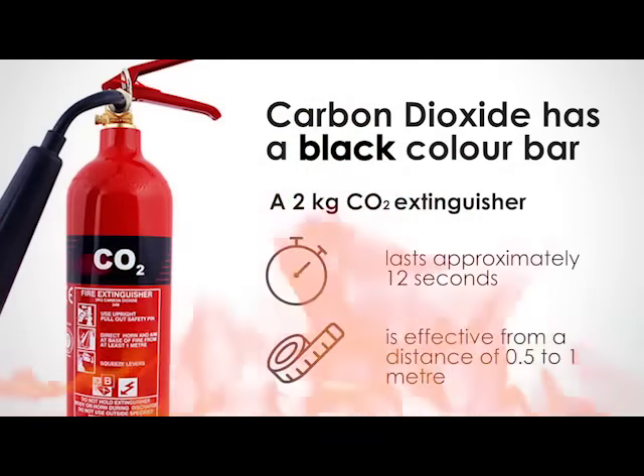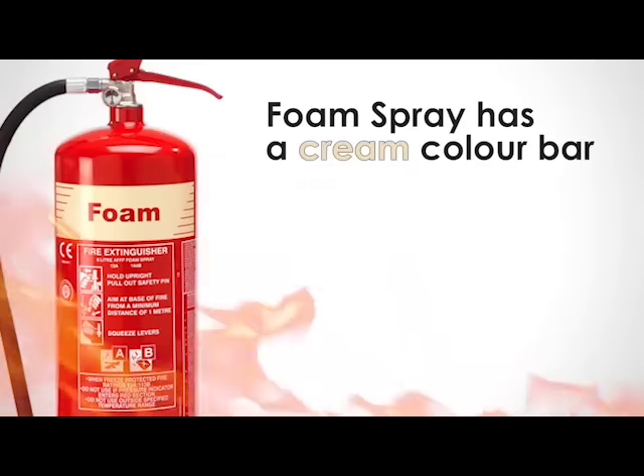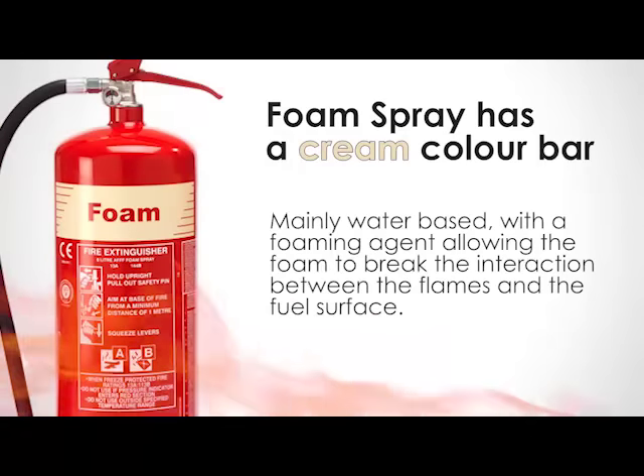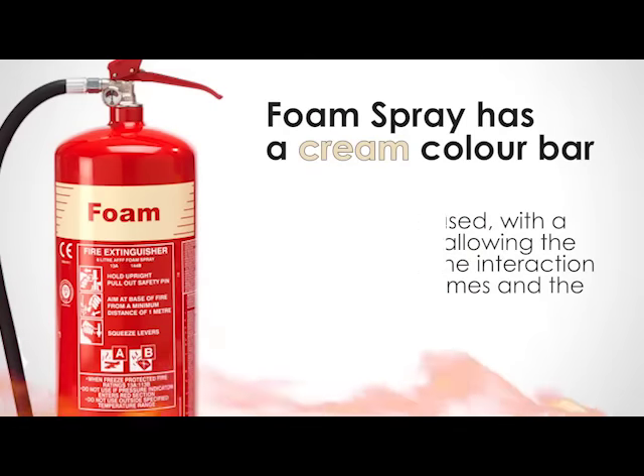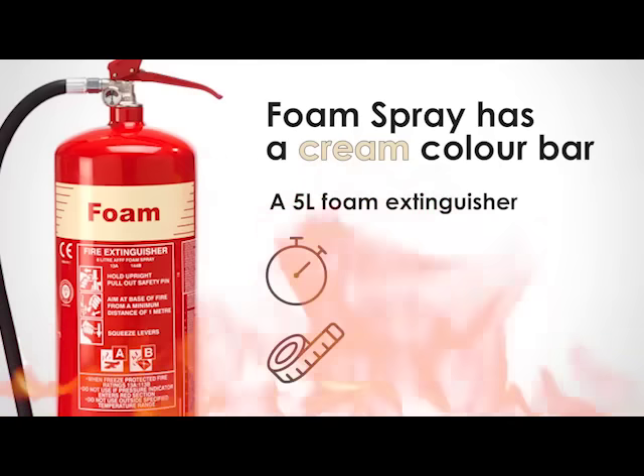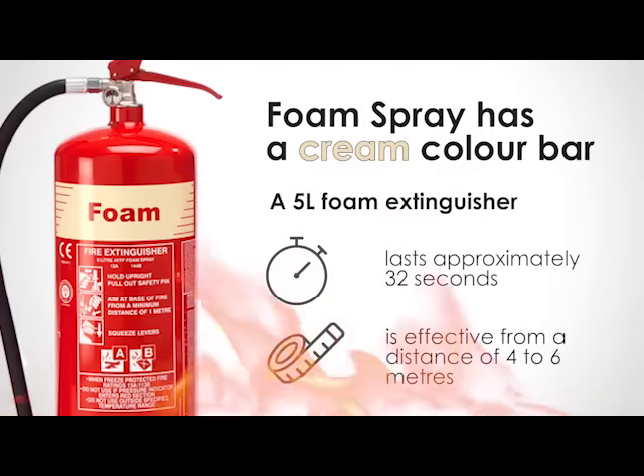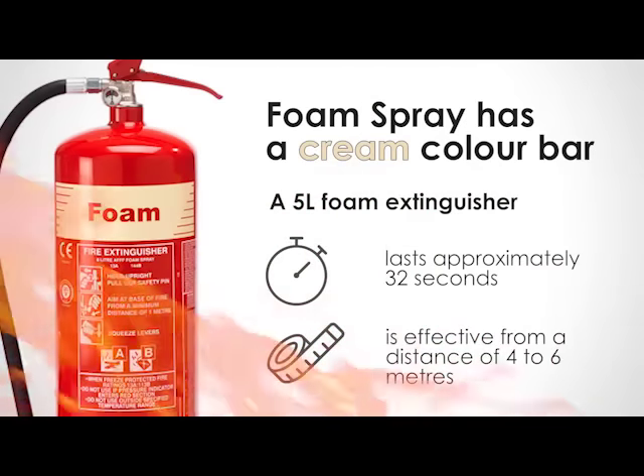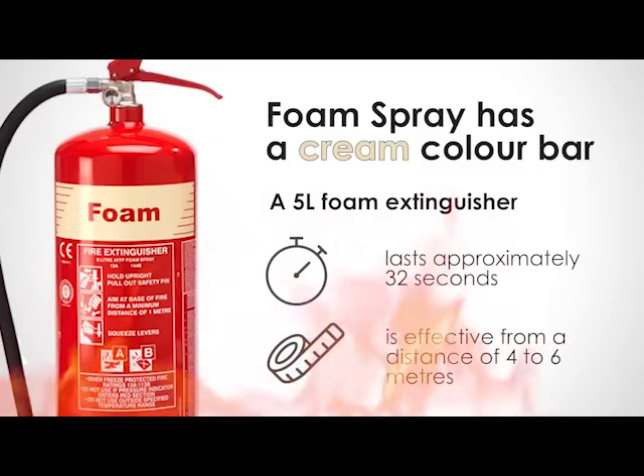Foam spray has a cream colour bar. These are mainly water-based with a foaming agent, allowing the foam to break the interaction between the flames and the fuel surface. A 5-litre total discharge foam extinguisher will last for approximately 32 seconds and is effective from a distance of 4 to 6 metres.